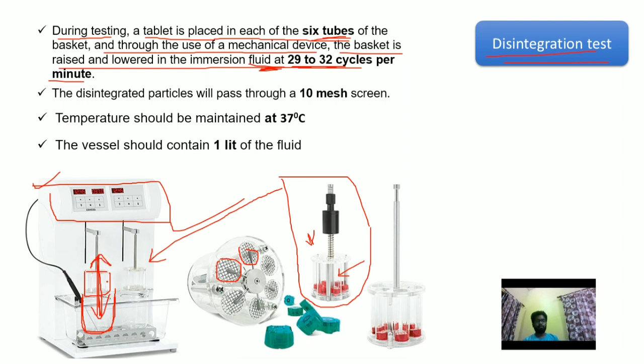The basket moves down and up within this fluid, going up and down 29 to 32 times per minute. So this information is very important.